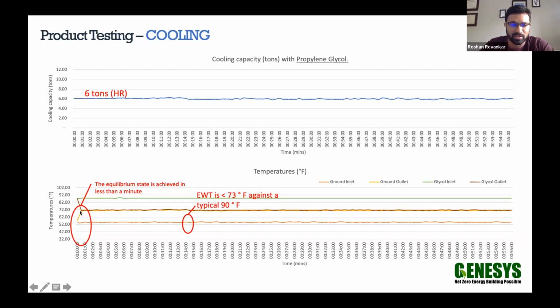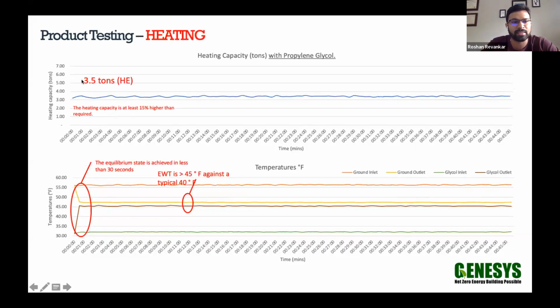One of the things you will observe is the approach temperatures between the open loop and the closed loop side is very, very small. In fact, it's minuscule. One of the reasons is the way the heat exchangers are designed, and secondly, the fact that it is stainless steel material. So this is for cooling mode. For heating mode, the 6-ton unit could produce 3.5 tons of heat extraction. So you add another ton on the compressor side, so nominally 4.5 to 5 tons for the 6-ton CLAD unit.